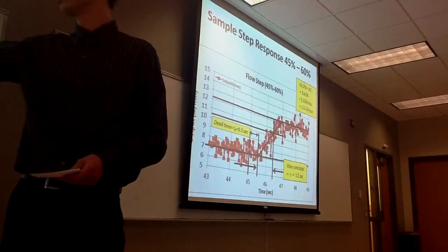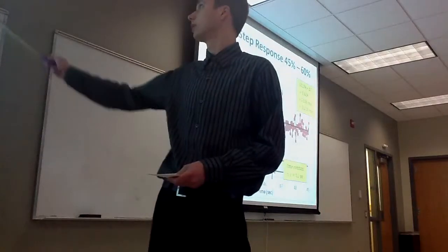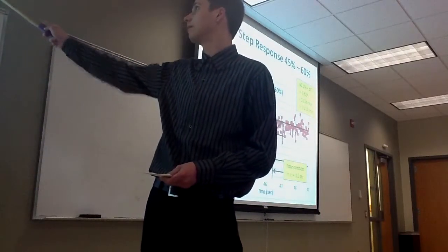The dead time was 0.5 seconds. The time constant was found using the Fit2 method, and this method involves taking the range of the output, which was 5.1 pounds per minute, and the time constant was found to be 1.2 seconds.